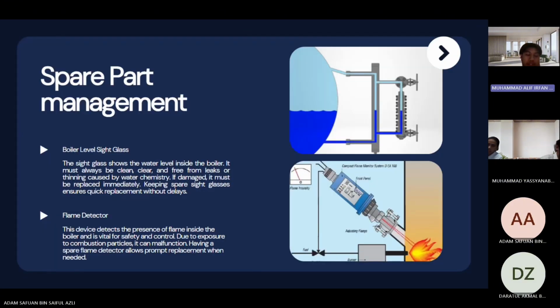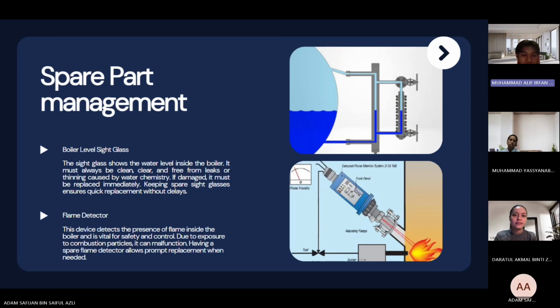Spare part management. First, boiler level sight glass. The sight glass shows the water level inside the boiler. It must always be clean, clear, and free from leaks or thinning caused by water chemistry. If damaged, it must be replaced immediately. Keeping a spare sight glass ensures quick replacement without delays.